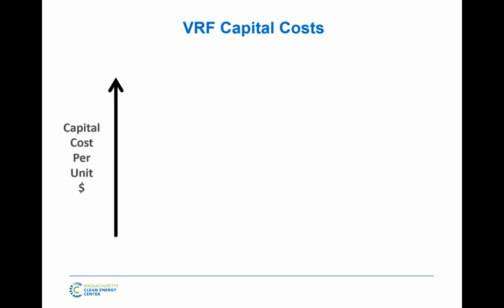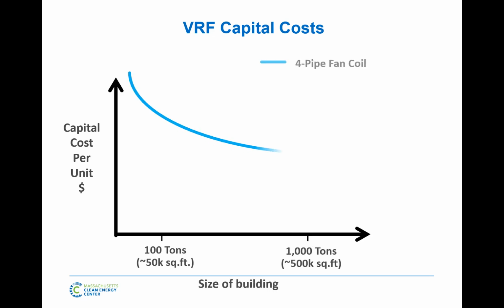So the interesting thing to look at next would be capital cost per unit dollars. If we look at something like this, this curve would be a typical 4-pipe fan coil. JS mentioned before, it is possible in a very large system to get something like a magnetic bearing chiller that's going to be as or more efficient than a VRF system, but it really only makes sense when you're doing a 1,000-ton building, or a very large building. So that kind of looks at when VRF came to the United States and watching its growth over the past several years, as we see the type of buildings we're involved in.